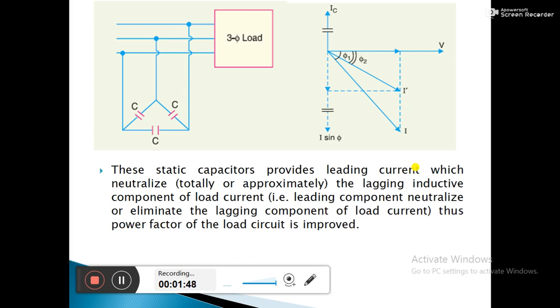Here you can see there is a three-phase load, and we are connecting the capacitor in parallel with the load. These static capacitors provide leading current which neutralizes the lagging inductive component of the current, thus improving the power factor of the load circuit. In the phasor diagram, we have drawn the phasor diagram for the inductive load, where the current is lagging the voltage.